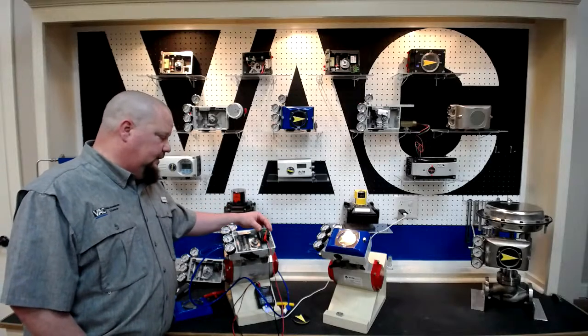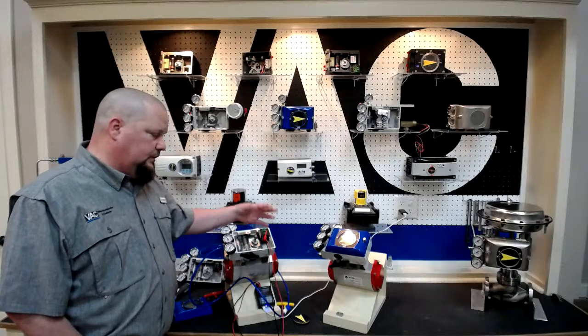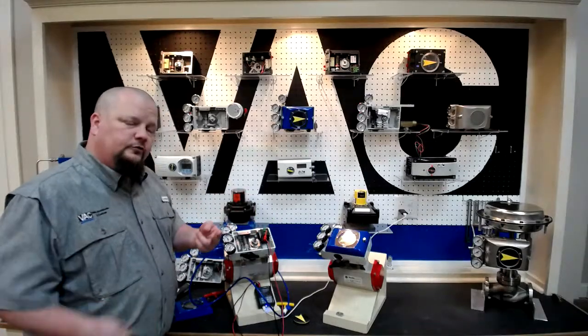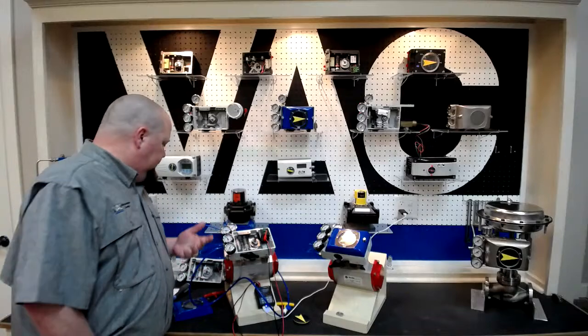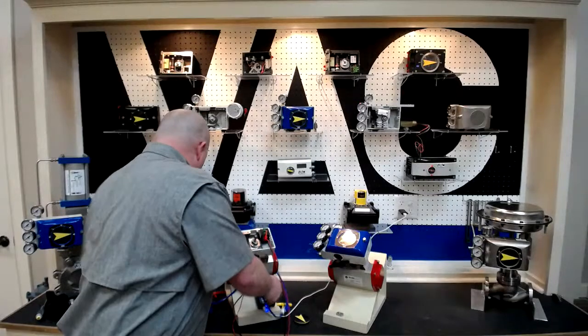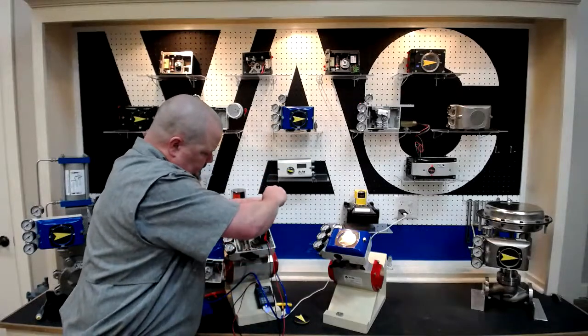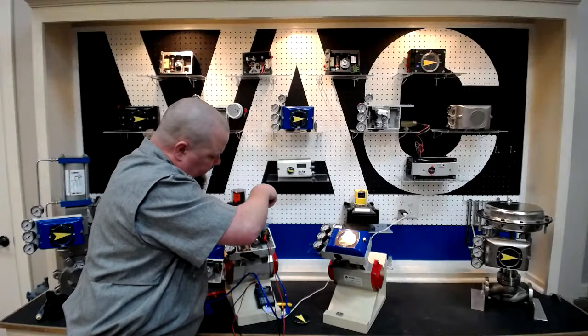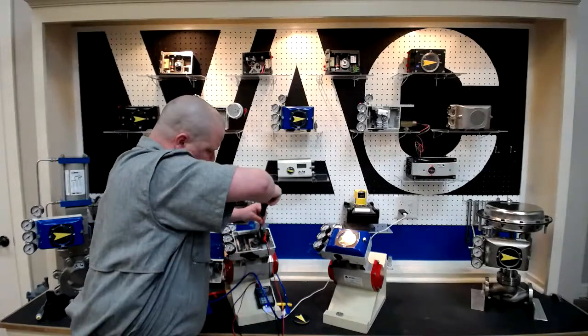If it's an electro-pneumatic with an I2P, generally what we'll do is pull this I2P out and look, there are 2 filters on the back side. We'll pull one here and show you. We'll look at those filters and see if they're discolored. They're really white filters.